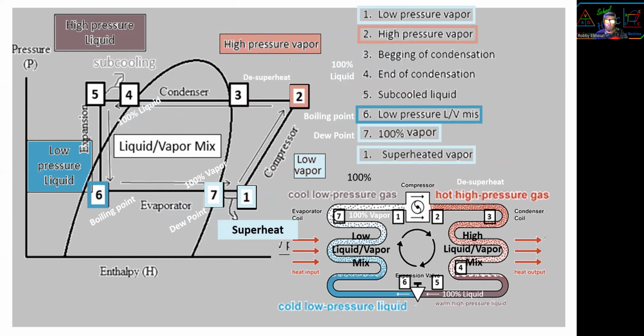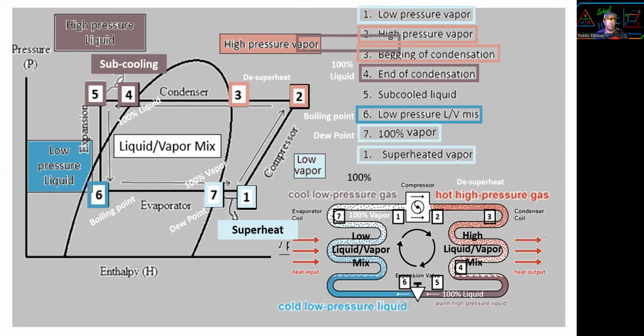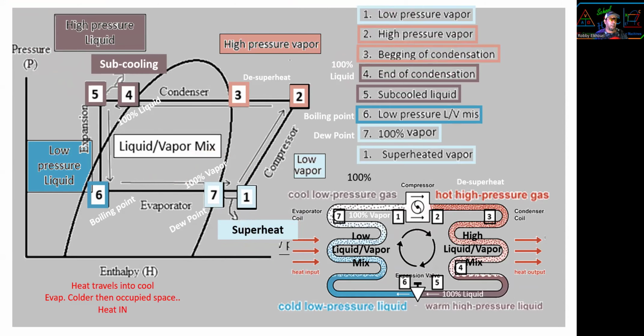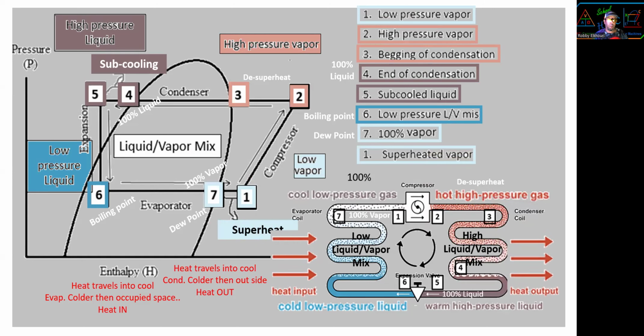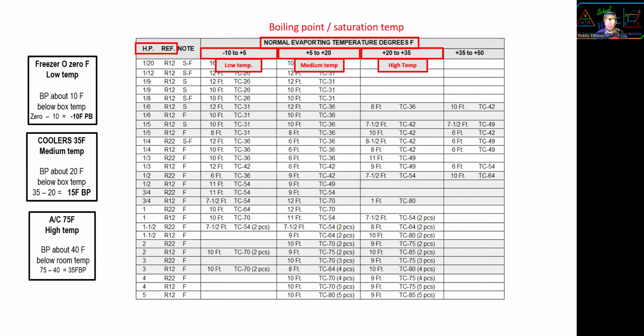In the condenser, first we do desuperheat. Number 3, beginning of condensation. I guess you could call that a bubble point. And number 4, end of condensation. And number 5, subcooling. And we have, of course, high pressure. It's not hot anymore now. The temperature is warm, high pressure liquid. Enthalpy is the heat traveling into the cool evaporator, cold, that occupies space. Heat travels into the cool evaporator, and the condenser is warmer than the outside air, and heat goes out.